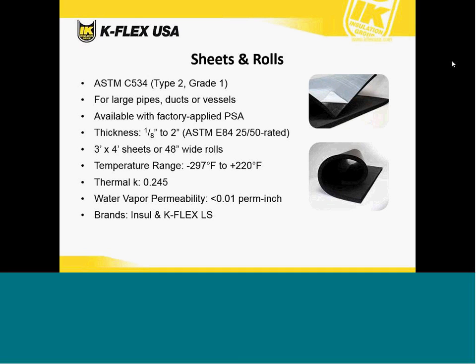Sheets and rolls. These are ASTM standard C534 Type 2 Grade 1. These are used on large pipes, ducts, or vessels, available with or without the factory-applied PSA, which is your pressure sensitive adhesive. These are available from 1/8 of an inch up to 2 inches, again 25/50 rated all the way up to 2 inches. 3-foot by 4-foot sheets or 48-inch wide rolls. Same temperature range, thermal conductivity, and water vapor permeability as the tube product.